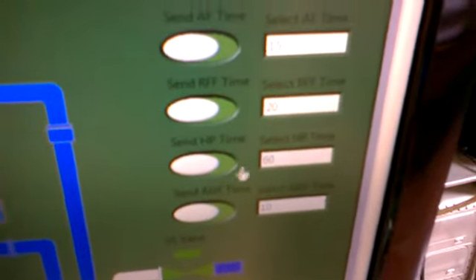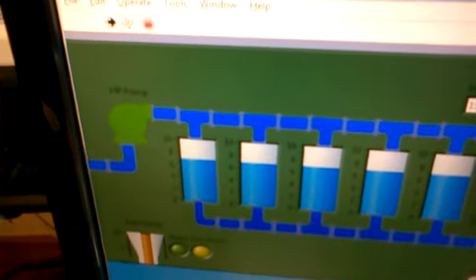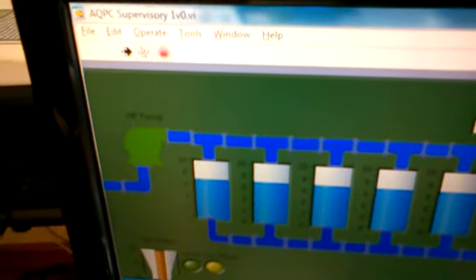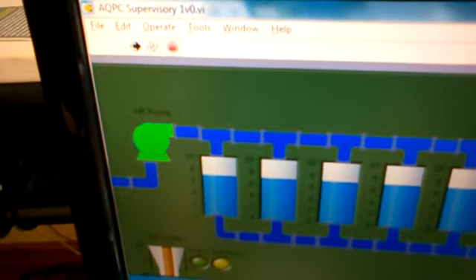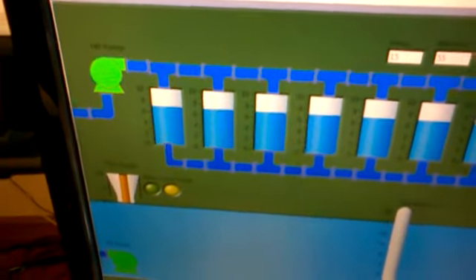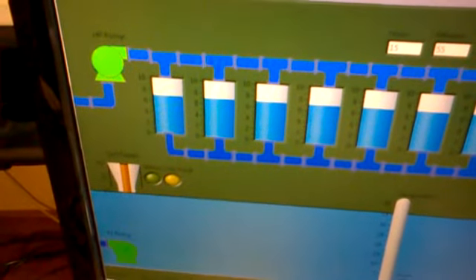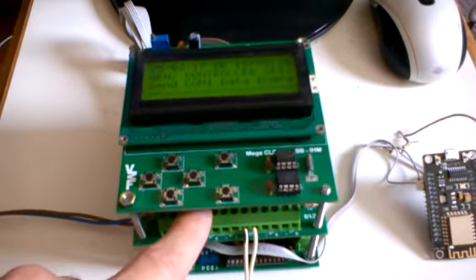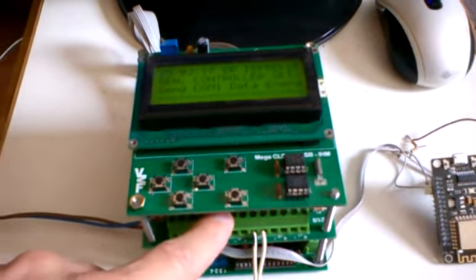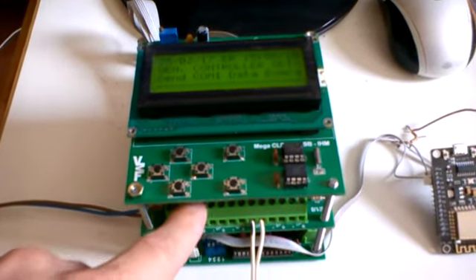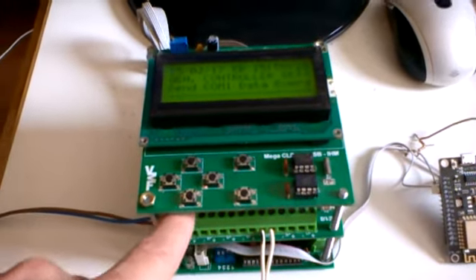So I'm gonna set the high pressure pump to, let's say, 60 seconds. I turn it on and after eight seconds we're gonna see the pump light up. Well, there it is. The relay clicks first on the I/O module. I'm actually using a digital one. It differs from the one that I have there on the side. On the side I have an analog one but this is one just for test so it works just fine.